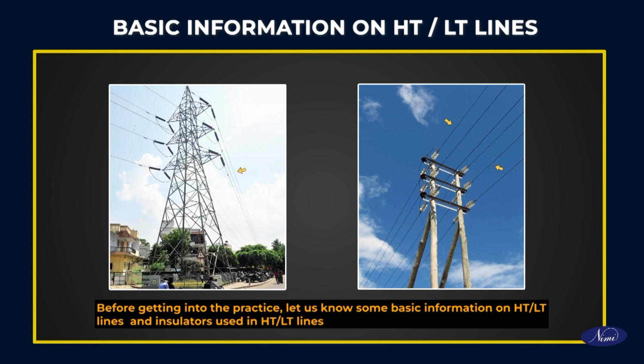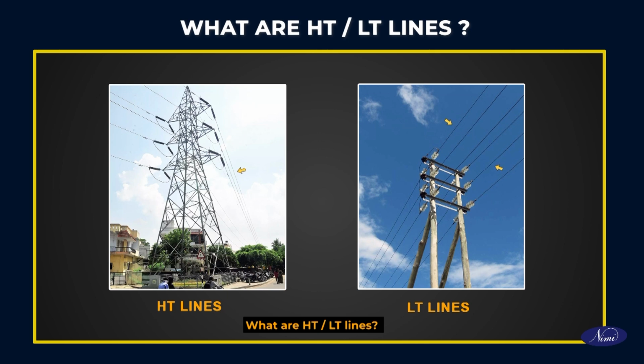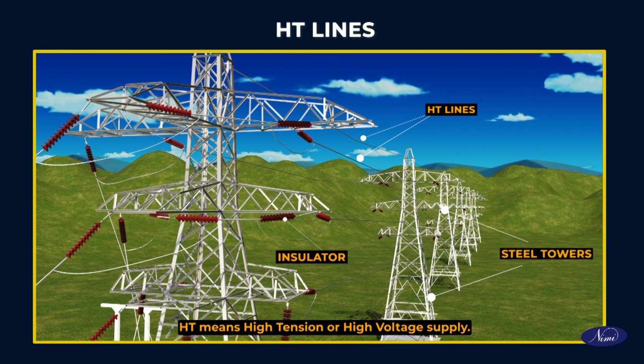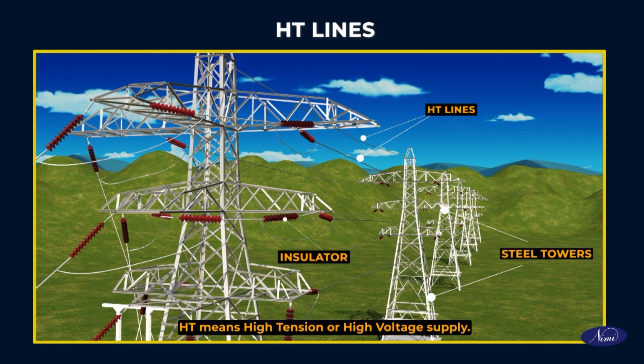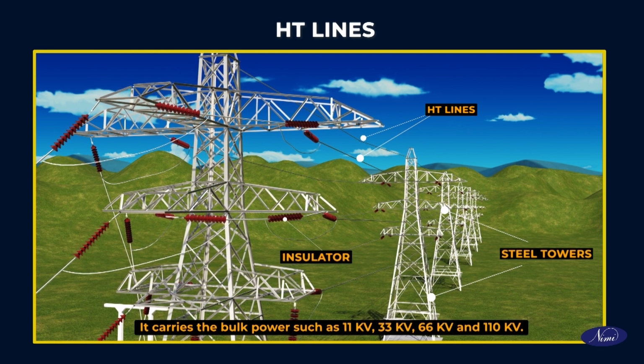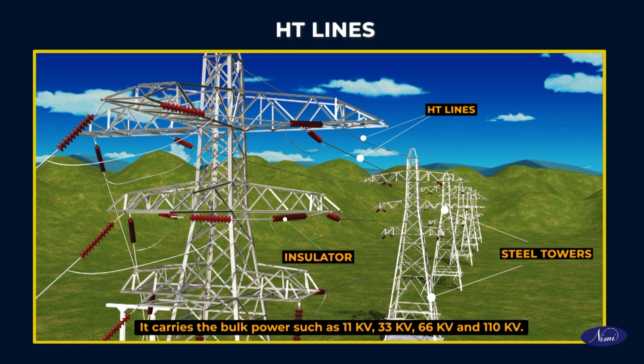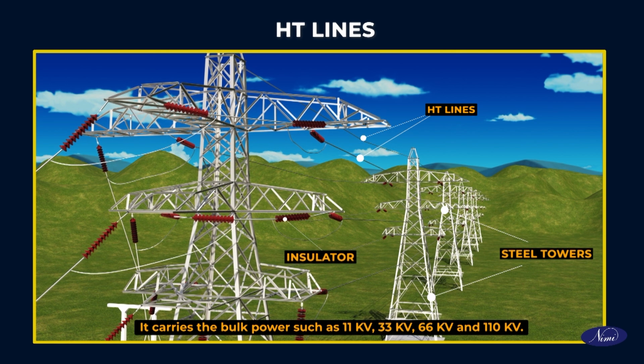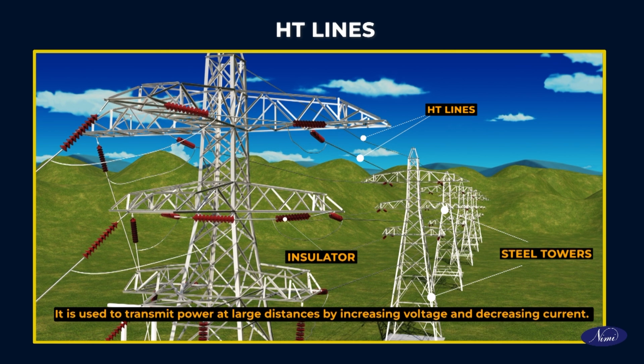Before getting into the practice, let us know some basic information on HT, LT lines and insulators used in HT, LT lines. What are HT, LT lines? HT means high tension or high voltage supply. It carries the bulk power such as 11 kV, 33 kV, 66 kV and 110 kV. It is used to transmit power at large distances by increasing voltage and decreasing current.